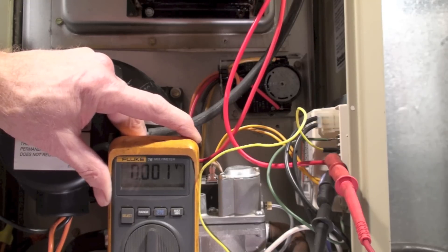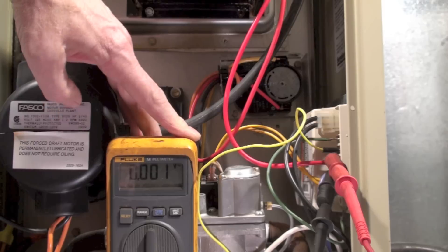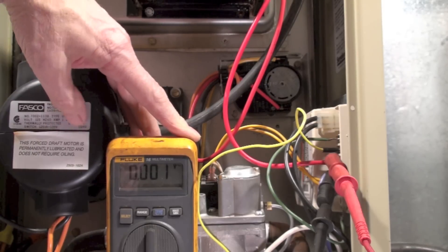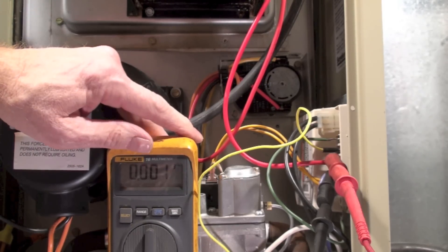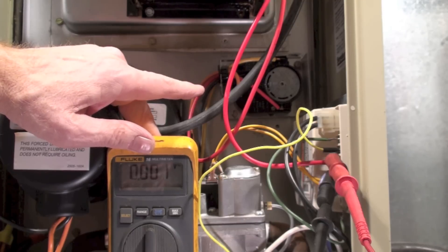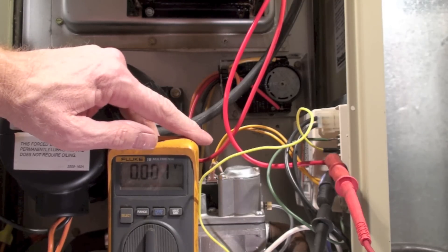things in the way here: one is a centrifugal switch on the blower up above, there's a pressure switch, and there is the limit switch here. Let's see if we can figure out which one of these is open.